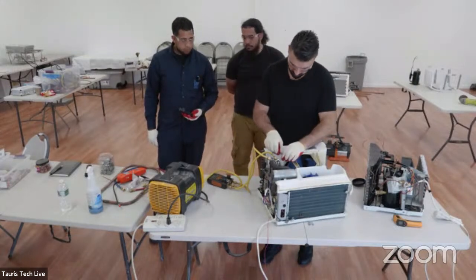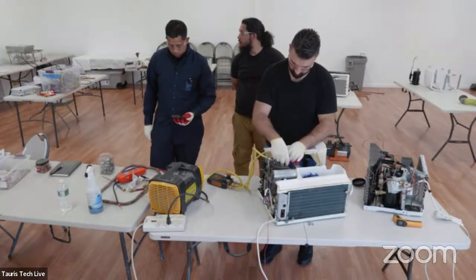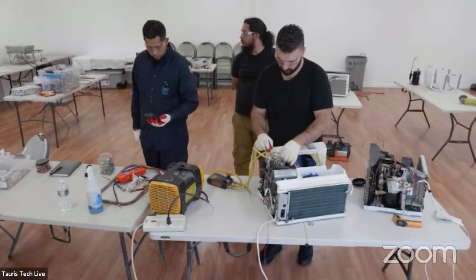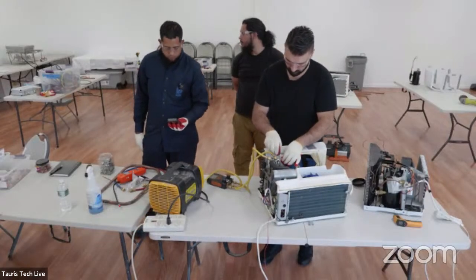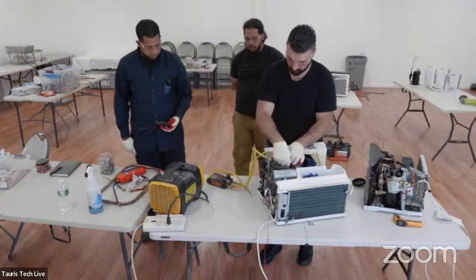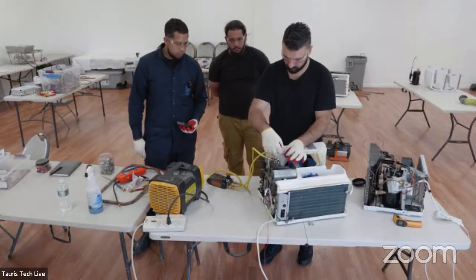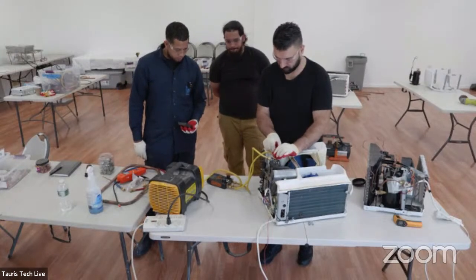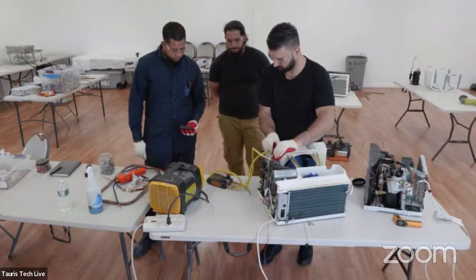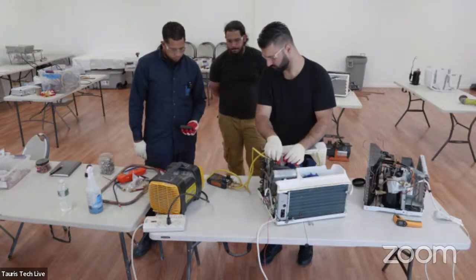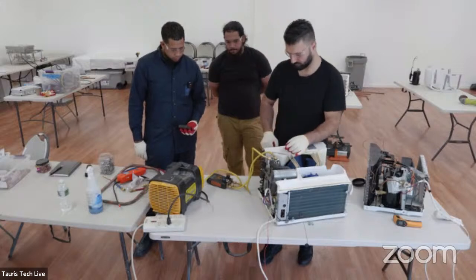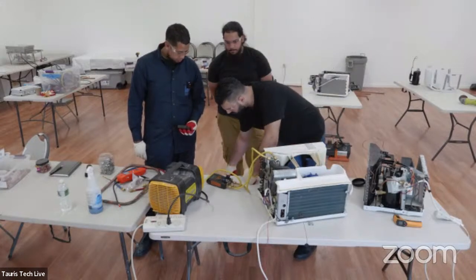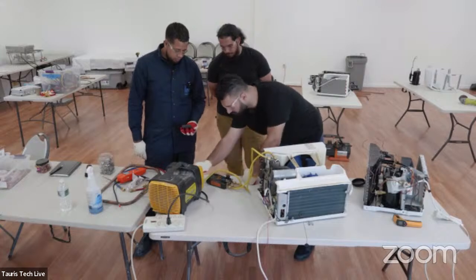Talk about what's emerging, talk about what you're seeing. So, like you were saying before, let's say we could turn the compressor on — you still need a recovery machine to recover, because it needs to suck it all through. You can't just go from the middle port of the gauge to the tank; it won't be enough to get it in there.